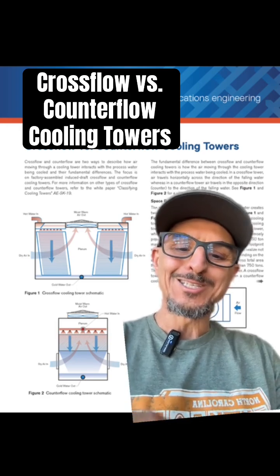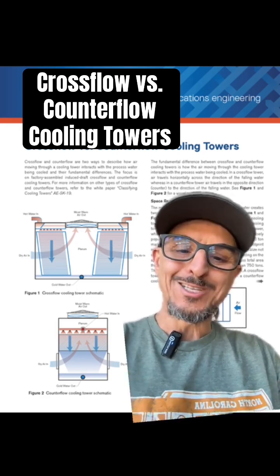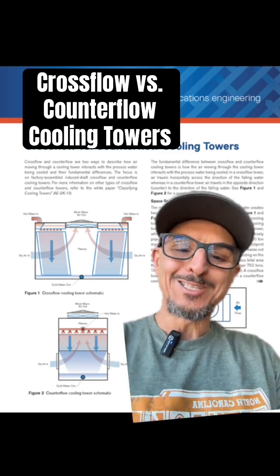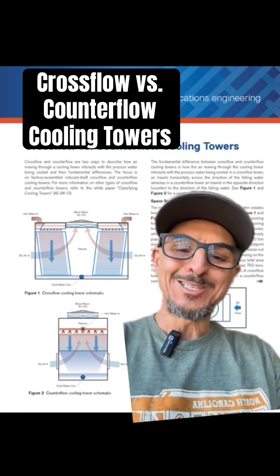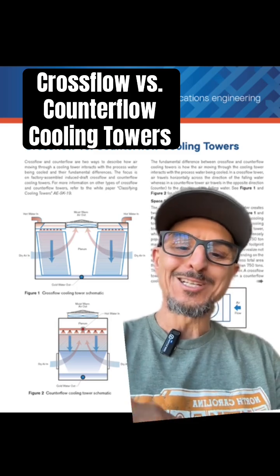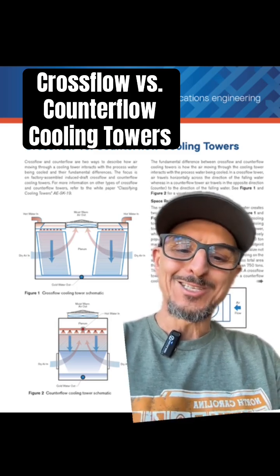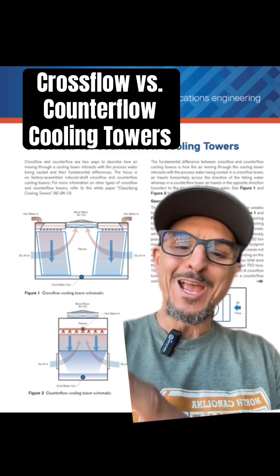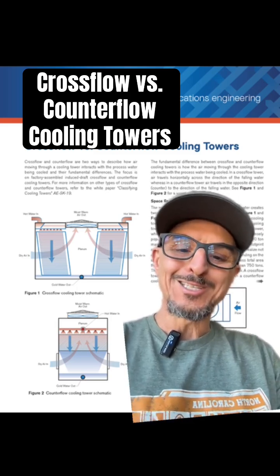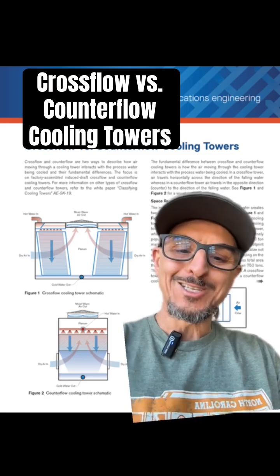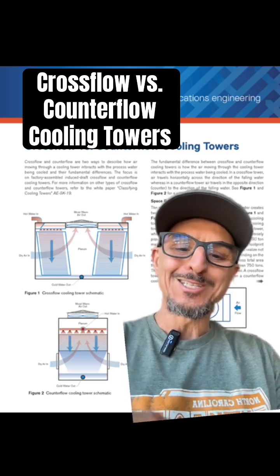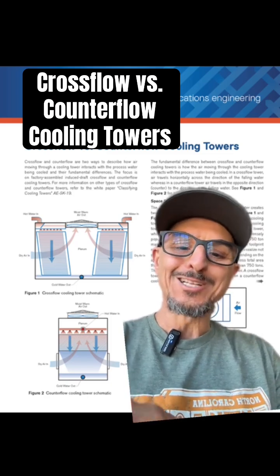There is a maintenance advantage to the cross flow as well. It's a little hard to see on this drawing, but there is a walkway basically between the fill where you could actually get in there, get to the motor easily if it's inside, get to the fan, the gearbox, et cetera. It's a little harder to do that on the counter flow.